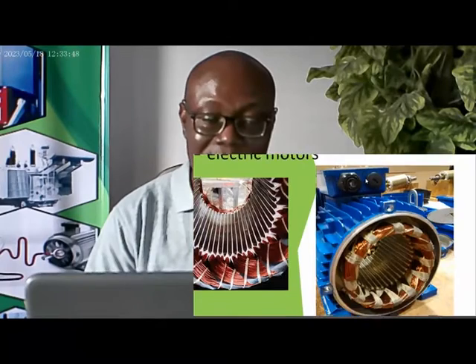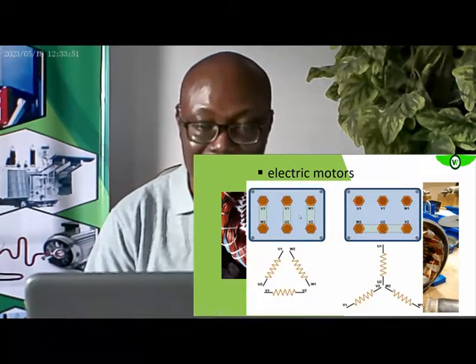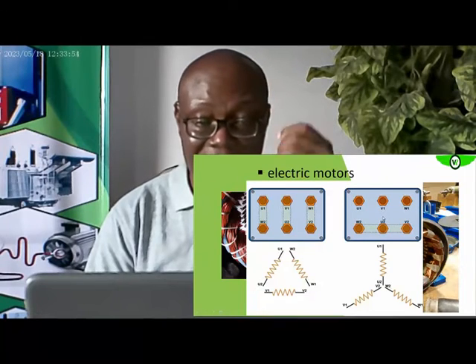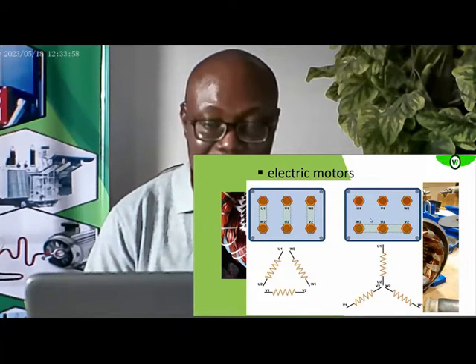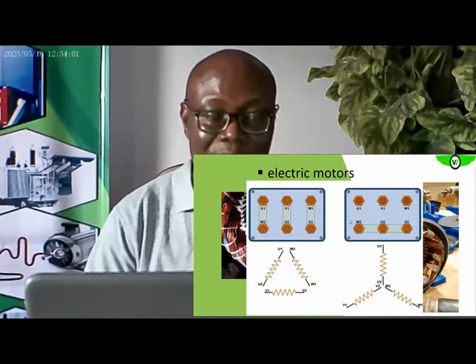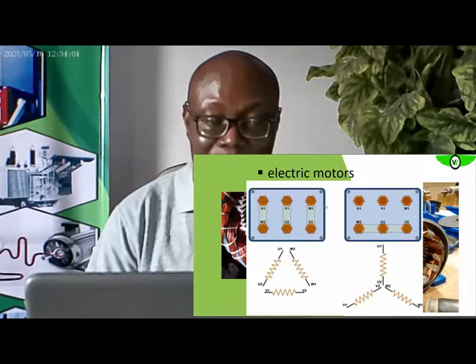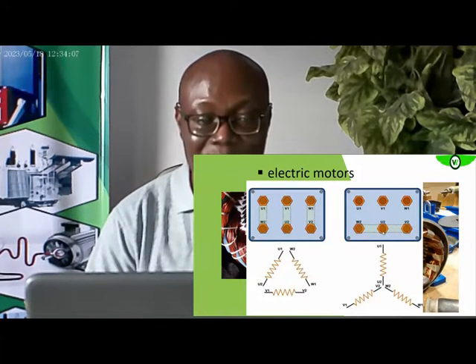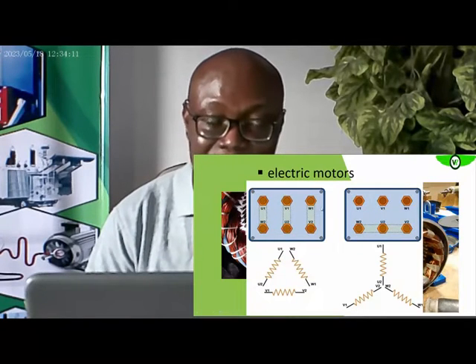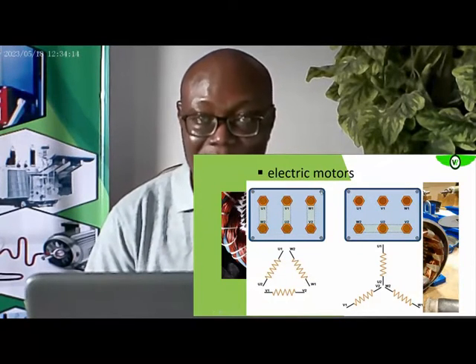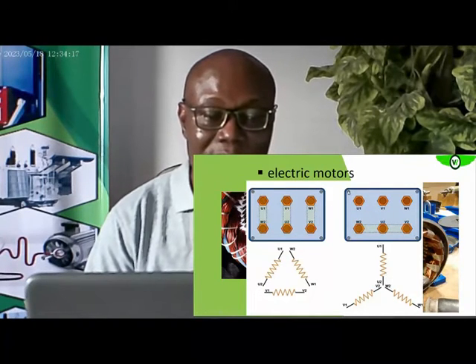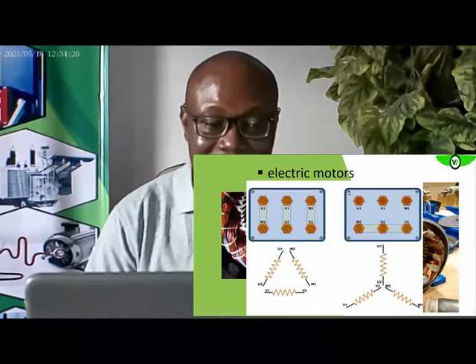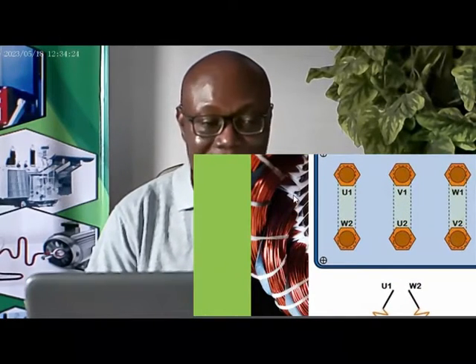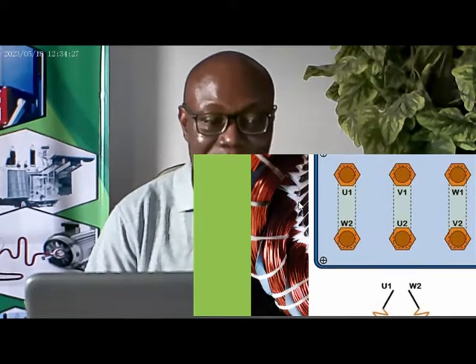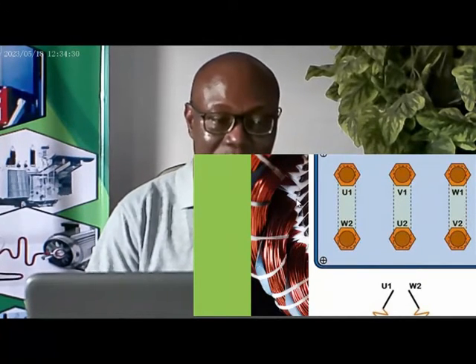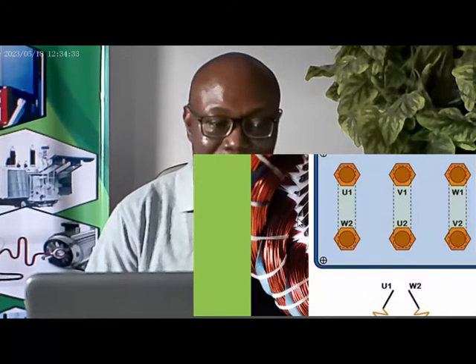It is either you have the delta connection or the star connection, as you can see. If you are carrying out insulation resistance tests between winding and ground, you can place one test probe on any of these terminals, and the other test probe on the ground, that is the frame of the electric motor, and then you apply your test voltage. The reading that you will get is the insulation resistance between the winding and ground. Remember what you are testing: this insulation in the slot that is separating the winding from ground.